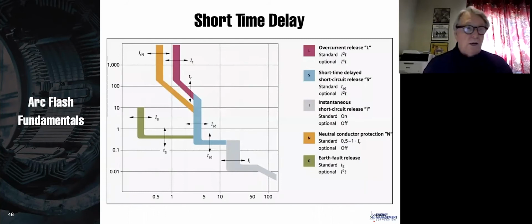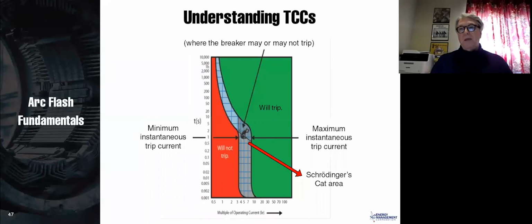So this is your short time delay. We use this commonly in engineering. There's your long time delay. You come down here and then you have a short time delay here, which says, I don't want to trip the main breaker to the facility or the main breaker on the switchboard because my swamp cooler shorted. I want to let the breaker closest to the swamp cooler interrupt that. And so what I'll do is just put a little time delay. I'll say 20 cycles of time delay here, and I'm not going to trip for 20 cycles, and that gives the lower breaker time to trip. Unfortunately, anything between this breaker and that lower breaker now has an intentional 20 cycle time delay, and that does wondrously horrible things for your calories. Now, here's a time current curve, and this could be, let's say, a fuse.